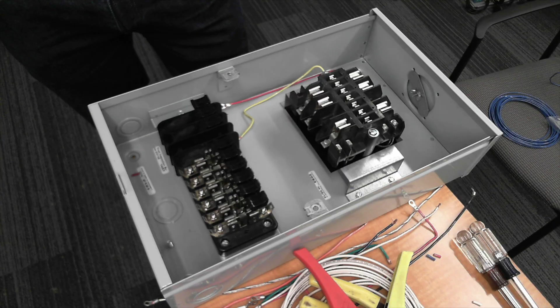How can you tell the difference between voltage and current, and where they go? As you see right here, we've got the black dividers. That'll be your voltage, so we can separate our voltages and nothing will come in there to short it out or cause an arc. This one right here is solid, doesn't have a test switch in it. That's going to be for our neutral. You never want to break the neutral, so you want to make sure it's there, solid, one continuous run.